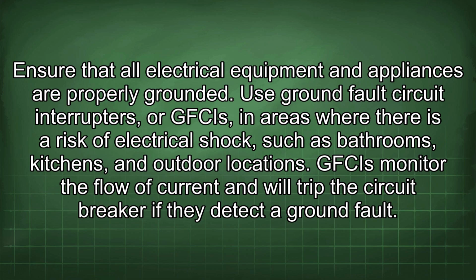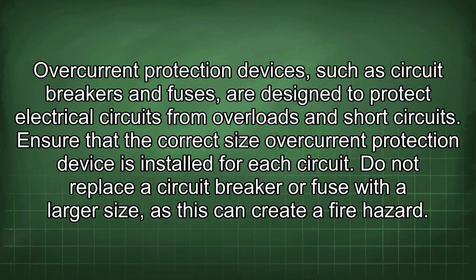Use ground fault circuit interrupters, or GFCIs, in areas where there is a risk of electrical shock, such as bathrooms, kitchens, and outdoor locations. GFCIs monitor the flow of current and will trip the circuit breaker if they detect a ground fault. Overcurrent protection devices, such as circuit breakers and fuses, are designed to protect electrical circuits from overloads and short circuits. Ensure that the correct size overcurrent protection device is installed for each circuit. Do not replace a circuit breaker or fuse with a larger size, as this can create a fire hazard.